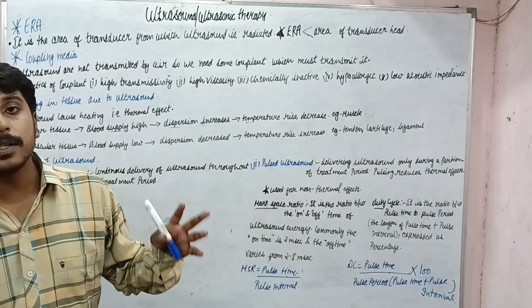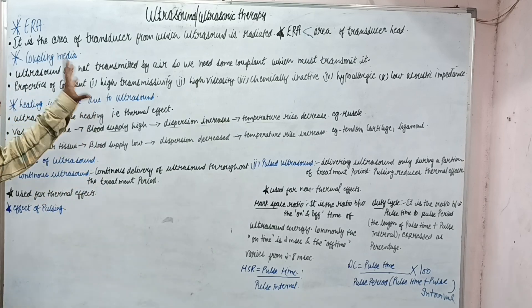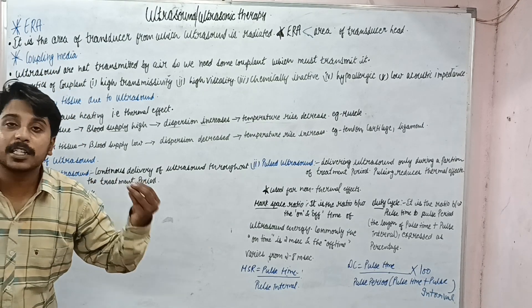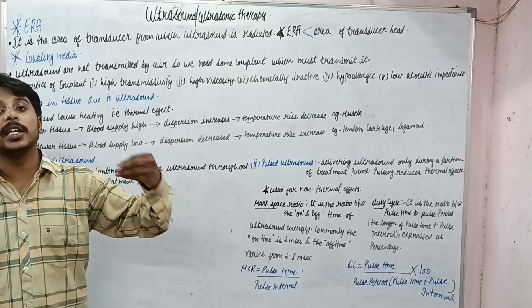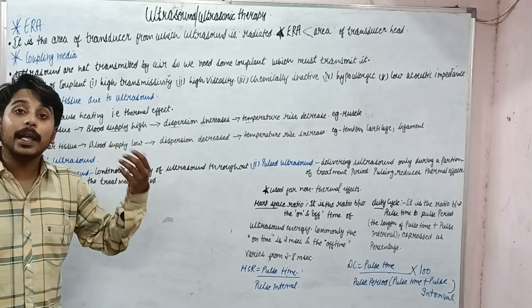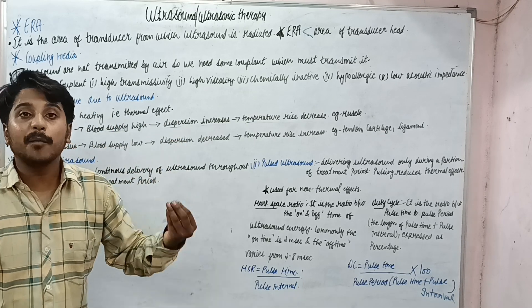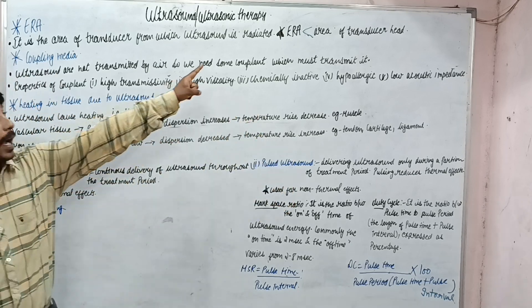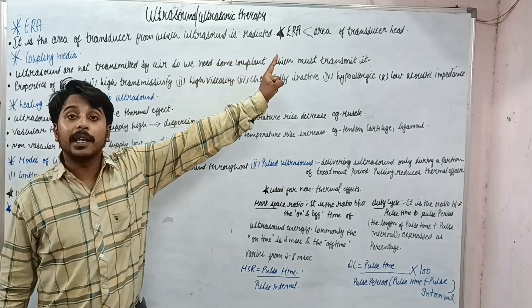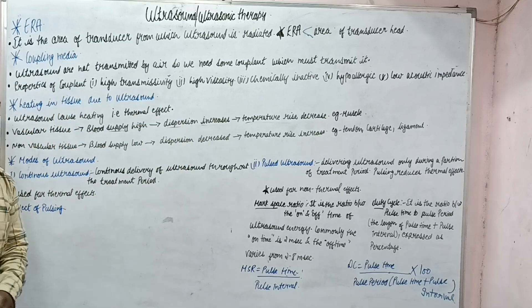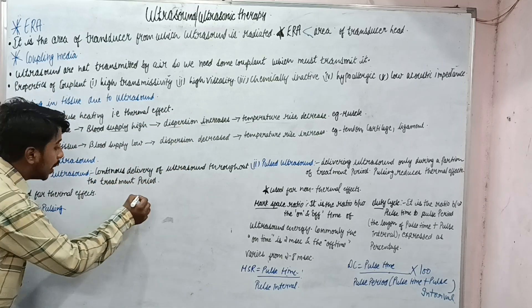My name is Vijay Kumar. ERA is expanded as Effective Radiation Area. It is defined as the area from which the ultrasound is radiated, and ERA is always less than the area of the transducer head.